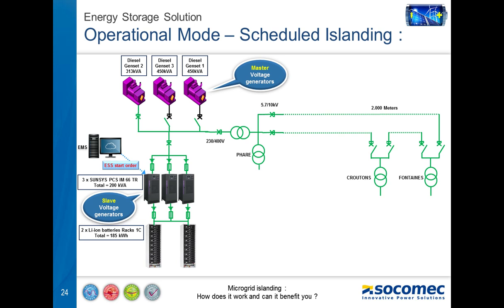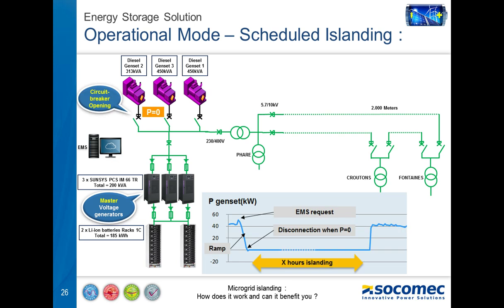When the energy storage startup is requested by the EMS, it asks for the power ramp of the PCS, thus going along with a ramp down of the genset power in order to erase completely the current flow on the genset circuit breaker. The energy storage system in this situation is in discharging mode to supply the load. Once the current and the power at the genset level are close to zero, the genset circuit breaker is opened by the energy management system without any disturbance on the load. It means that the load cannot see any perturbation. After the circuit breaker opening, the energy storage system switches automatically from the slave voltage generator mode to the master voltage generator mode. In this situation, the energy storage system ensures autonomously the balance between the local production and consumption, while the state of charge and the power of the PCS are within the operating range.